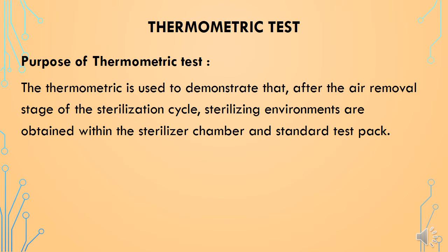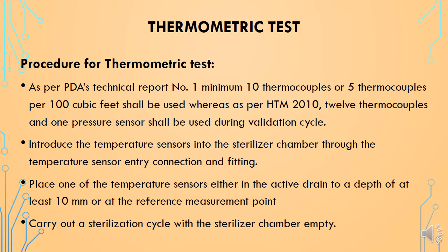The next qualification test is the thermometric test. Its purpose is to demonstrate that after the air removal stage of the sterilization cycle, sterilizing conditions are obtained within the sterilizer chamber and the standard test pack. As per PDA's technical report No. 1, a minimum of 10 thermocouples or 5 thermocouples per 100 cubic feet shall be used, whereas as per HTM 2010 (now known as EN 285), 12 thermocouples and one pressure sensor shall be used during the validation cycle.